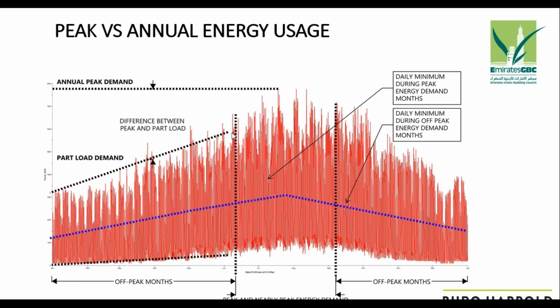So the building actually operates in a part load condition for maybe 90 to 95% of the time. It's important to know that if you provide enough PV to satisfy the peak demand, you'd actually end up with a net positive building.